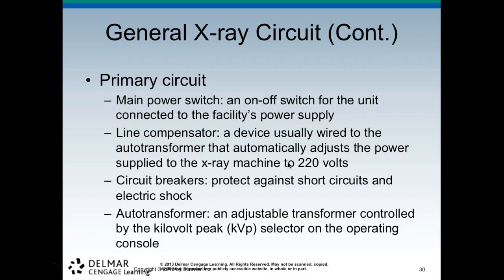So the primary circuit: the main power switch is an on-off switch for the unit, connected to the facility's power supply. There's a line compensator, a device usually wired to the autotransformer that automatically adjusts the power supplied to the X-ray machine to 220 volts. And there are circuit breakers. They protect against short circuits and electric shock, thank goodness. And the autotransformer is an adjustable transformer controlled by the kVp selector when operating the console.